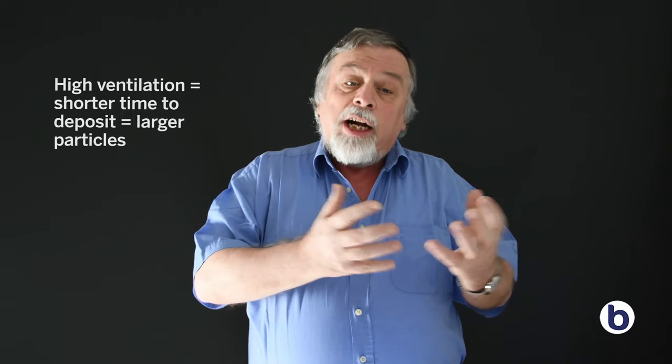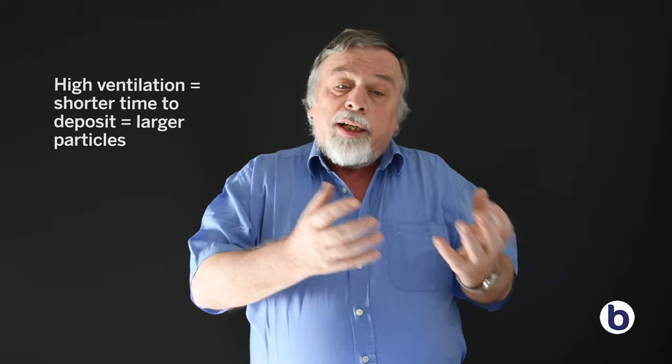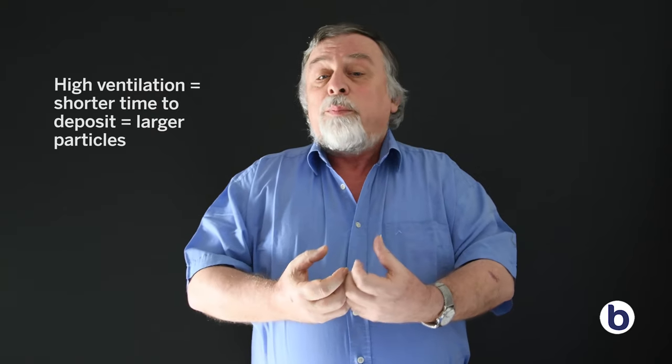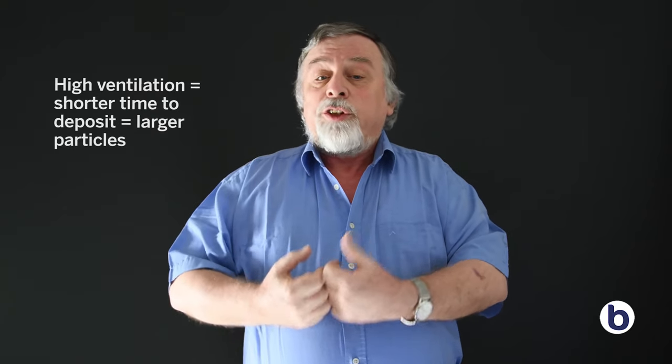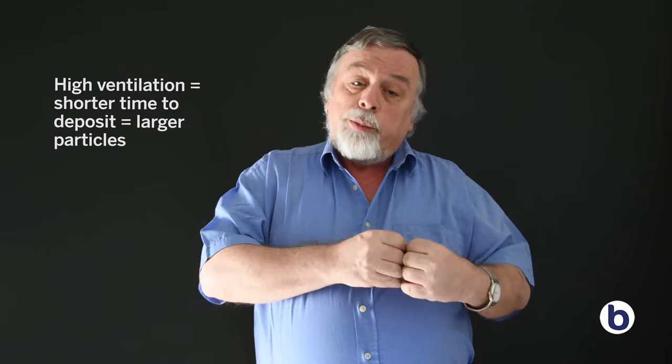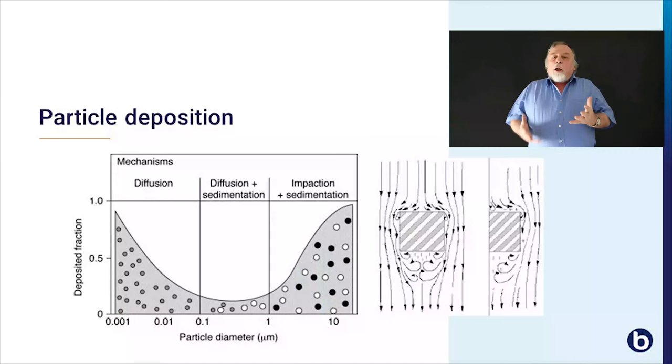The size of the particles that will deposit depends on the time air flow is inside the clean room. When the ventilation is high, the time a particle has to deposit is much shorter, so you will deposit larger particles inside the clean room.